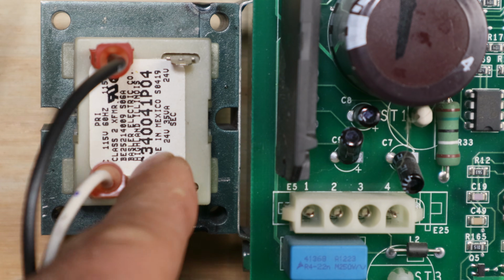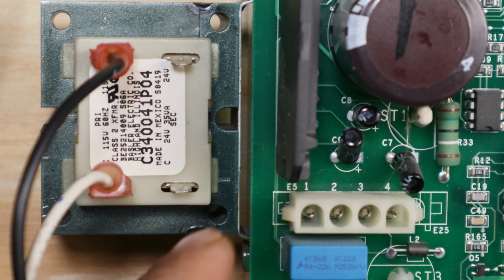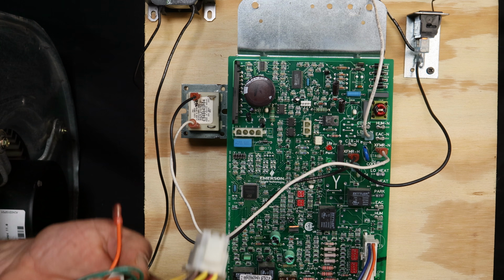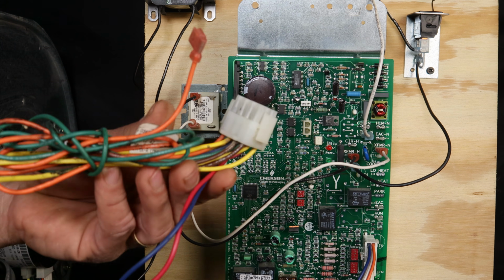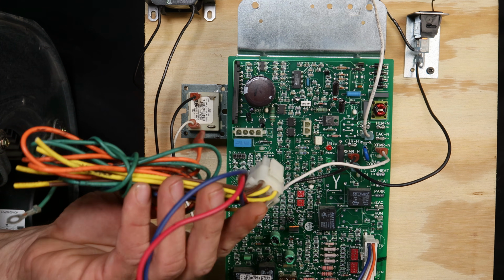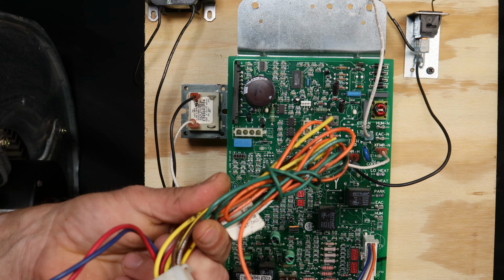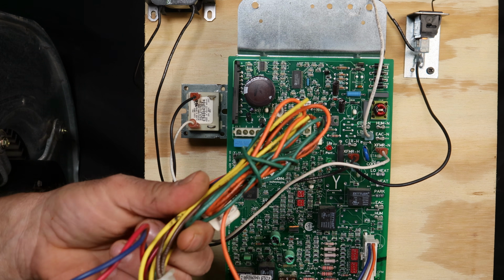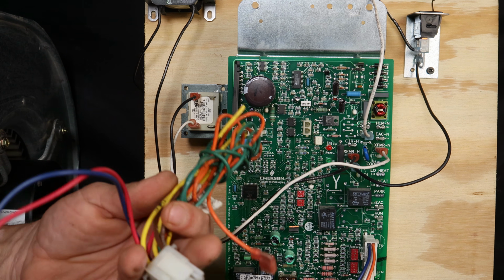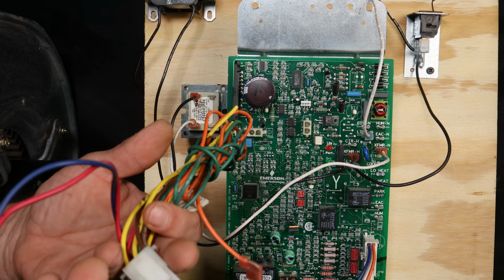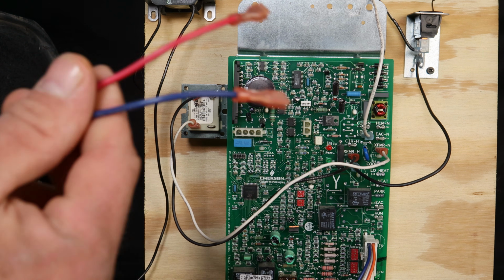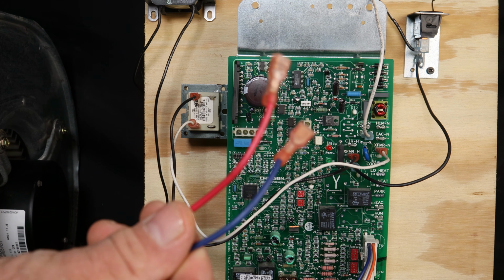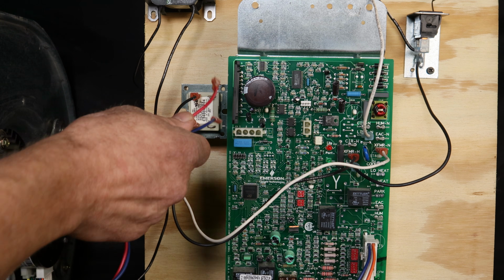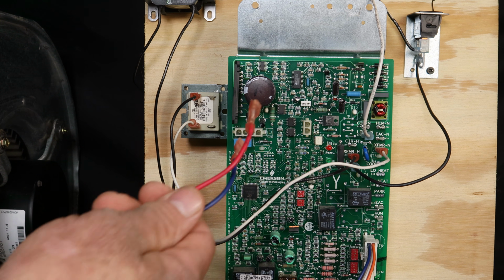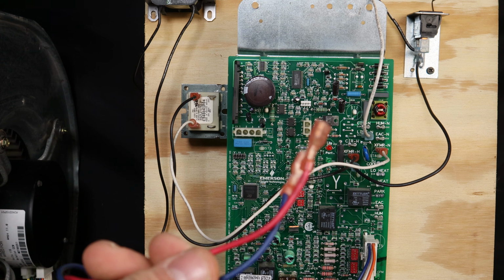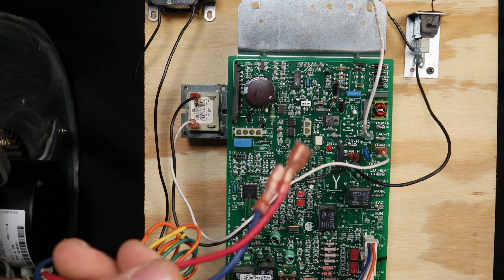Now we have to run our 24 volts from the secondary side of our transformer back to the control board. Now to do that on this particular setup here, we have a Molex plug with a bunch of wires coming off of it. Most of these wires are for the safeties in the heating circuit, which we're not going to get into today. I do have a video that goes deep into heating circuits on furnaces. You can watch that if you're interested. But we're just going to hook up these red and blue wires, which is 24 volts from the secondary side of a transformer that feeds to our control board, which we can use to control our system and run our blower motor.